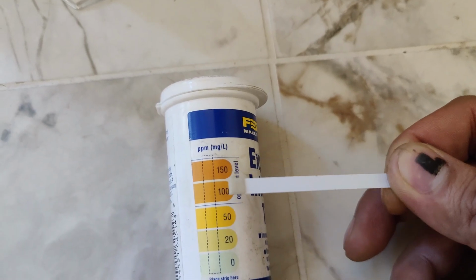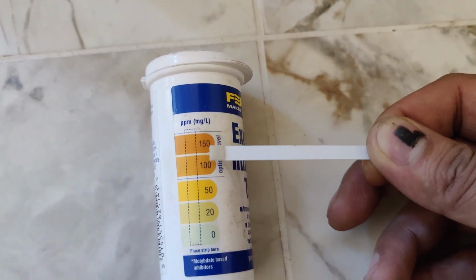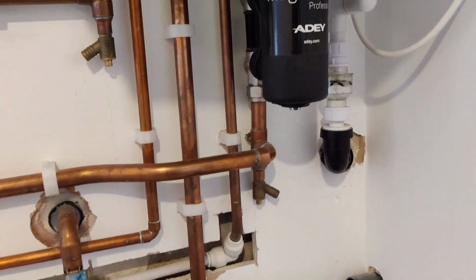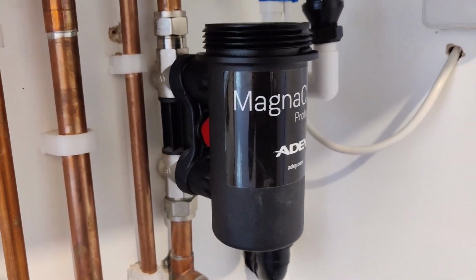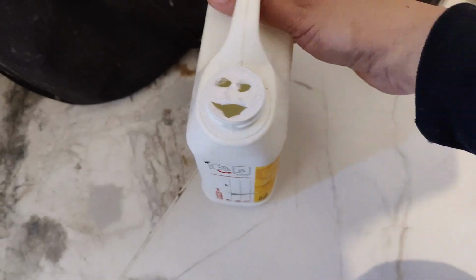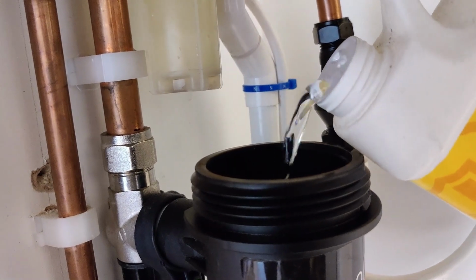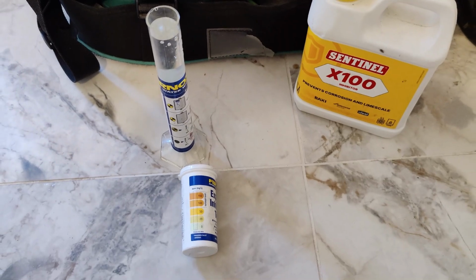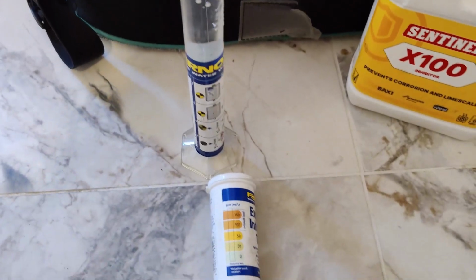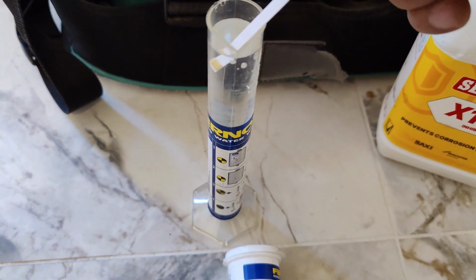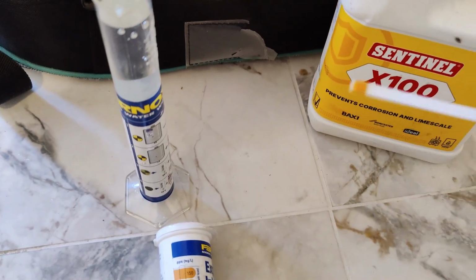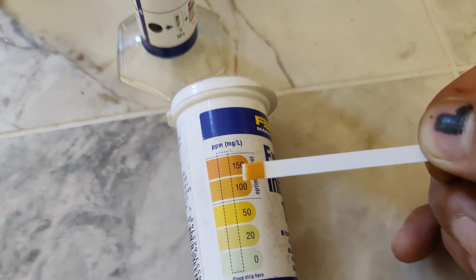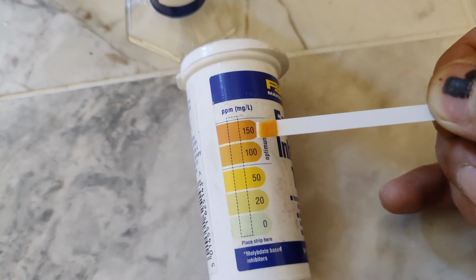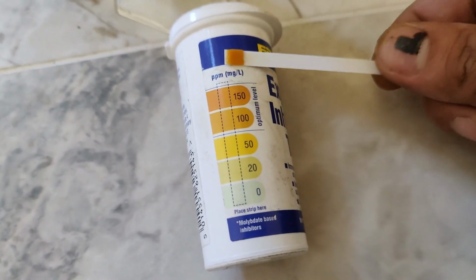because we need to be in this range, 100 or 150, and our test strip should show us this colour. So we're just going to top it up. The easiest way to put it in is to top it into the filter and retest, and that'll do the job. Okay, so I've topped up the inhibitor on the system, got some more water out of the system now. I'm just going to repeat the test. So dry off the excess liquid, and then within 10 seconds just compare. So I think we are perfectly fine now compared to what it was before.